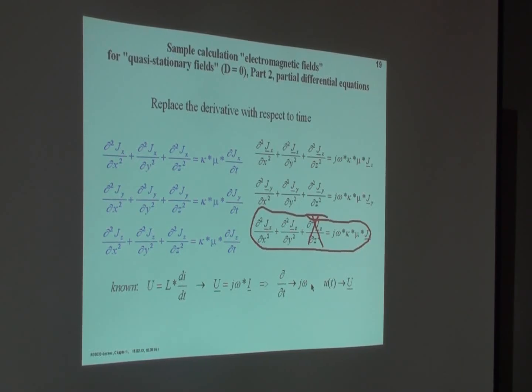It's a practical experience. You can't directly see it out of the differential equation, but in practice it is so, and we already examined it by measurement. The current is flowing at the surface, some millimeters on the surface. If you have a steel arm and put copper on it, it's flowing only in the copper. Maximum is 8 or 9 millimeters at 50 cycles per second, and at 60 cycles per second. The current density in the deep is a little bit smaller. It's only flowing on the surface, therefore it's not flowing in the steel.